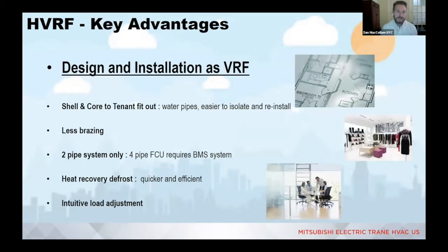A few more benefits of this system. I mentioned before that there's less brazing. You also get the benefits of a 4-pipe system in terms of simultaneous heating and cooling with only 2 pipes. The defrost cycle happens a little bit quicker than with typical VRF systems, but in our climate, defrost, at least in my experience, hasn't been a very challenging aspect to work around. But then lastly, intuitive load adjustment. That's just a fancy way of saying that this system is fully variable. So the refrigerant flow can vary, the water flow can vary, the fan speeds can vary. Everything will move and track to hug your set temp as tightly as possible.